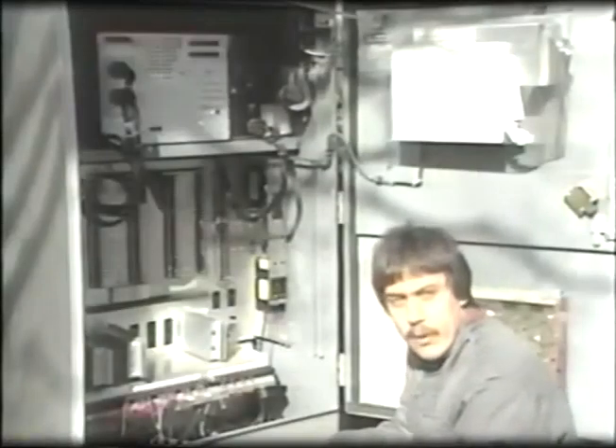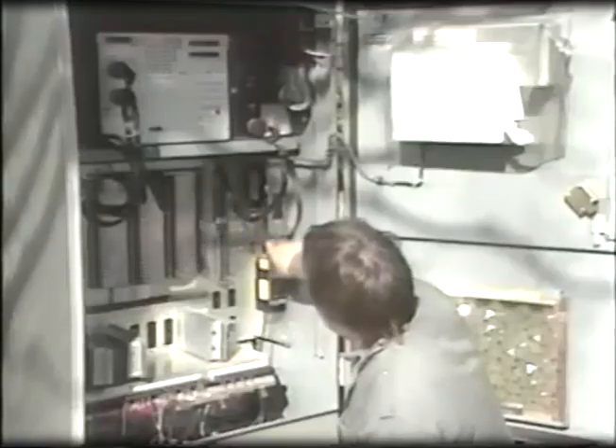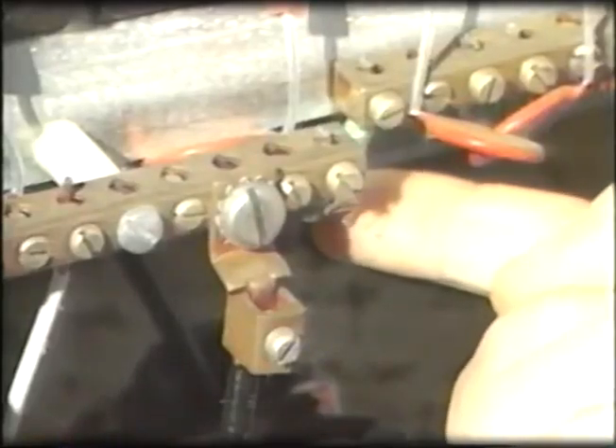Here's an example of a fairly well-designed controller cabinet. Power and communications cables enter through the bottom of the cabinet. Power cables run up to circuit breakers. We have EDCO suppressors, followed by an RFI filter in parallel with the EDCO suppressor. The ground rod is a 5/8 inch galvanized rod with a copper bolted connection. Solid number 6 runs over to the chassis. The neutral and the ground are connected because code permits it.